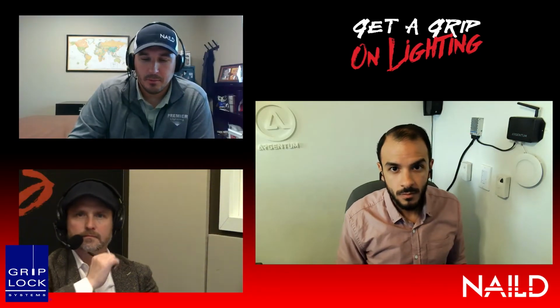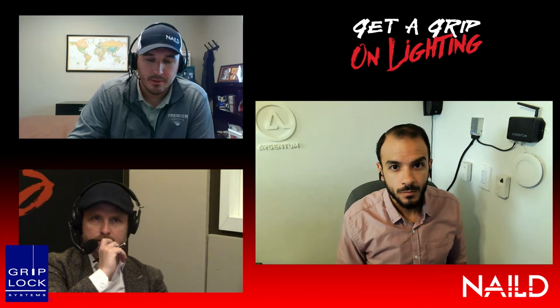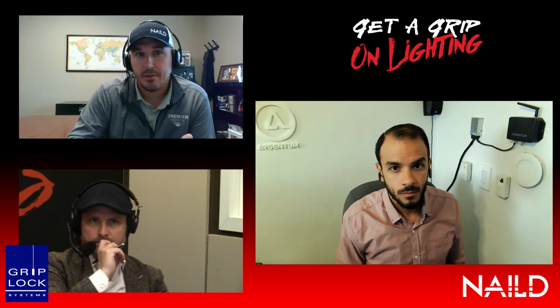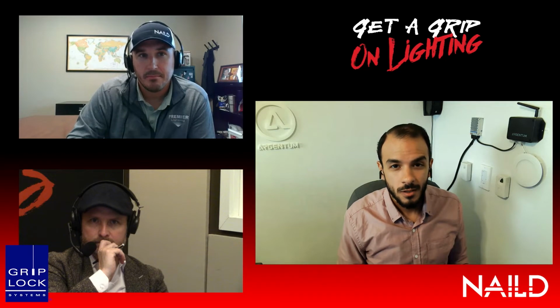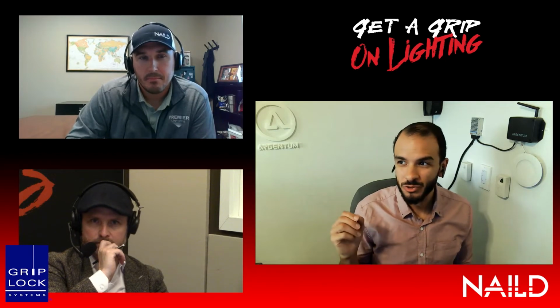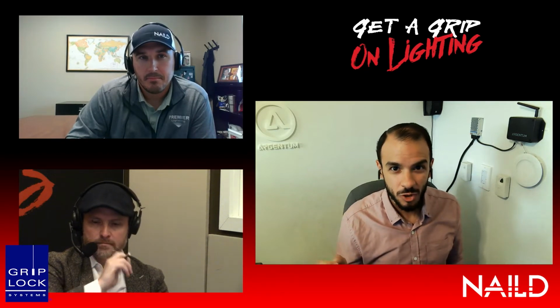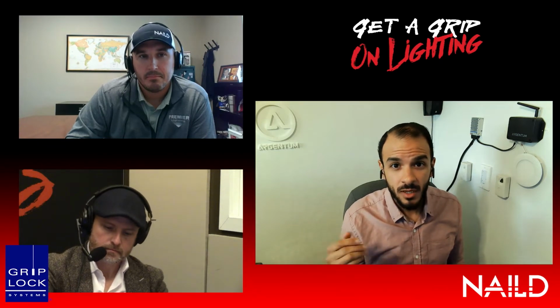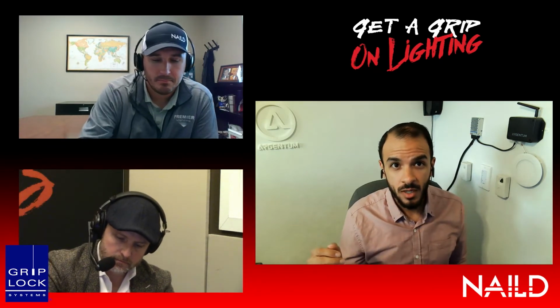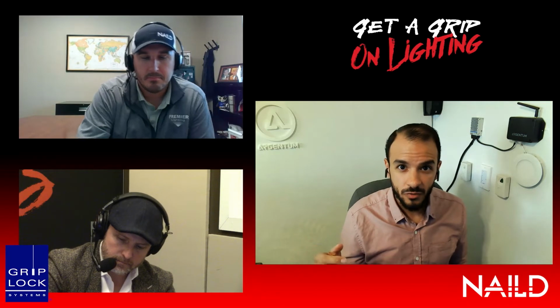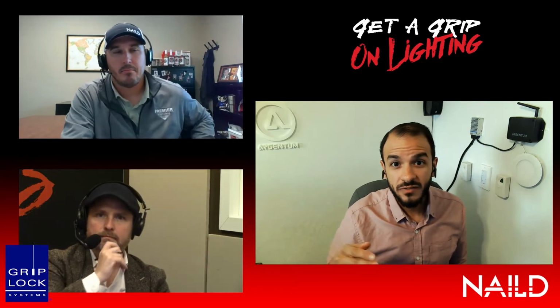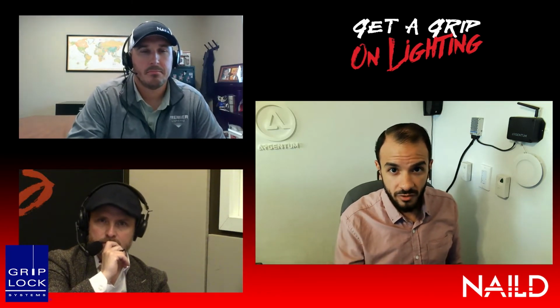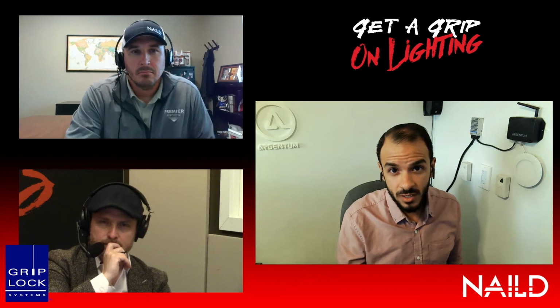So the real benefit from a lighting standpoint is that it's going to last longer and save energy if you go with DC. There's a big benefit for power consumption, especially for new builds. In the retrofit scenario, doing an LED retrofit means longer lifespans, so instead of your driver being the point of failure, your point of failure becomes the LED.